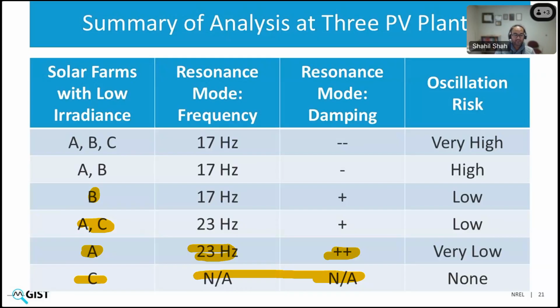But when we connect another plant, either plant A or plants A and C together with B, then, as I showed, the resonance mode moves to 17 Hertz from 23 Hertz, which is created by plants A and C, and the damping is quite negative, and we have a high risk of oscillation. So in summary, plant B is a necessary ingredient for these oscillations, particularly when it operates at low irradiance conditions. And then plants A and C make it worse.